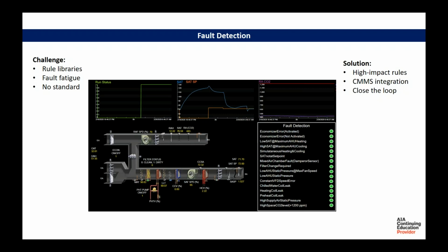But even if the sensors were accurate to 0.1 of a degree, which they're not, but if they were, do you really think, or do you really want to ask somebody to go troubleshoot why the supply air temperature at this air handler is 57 instead of 55, right?